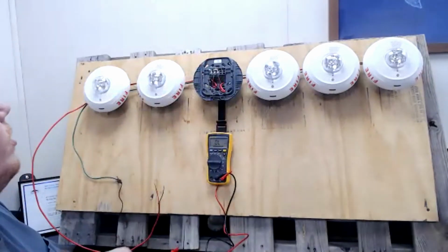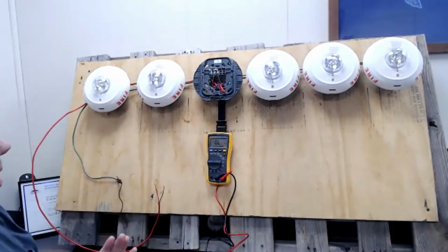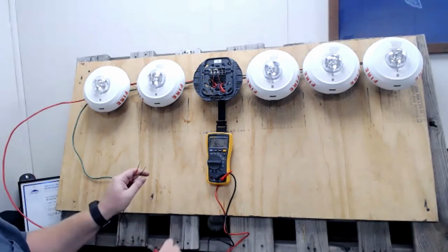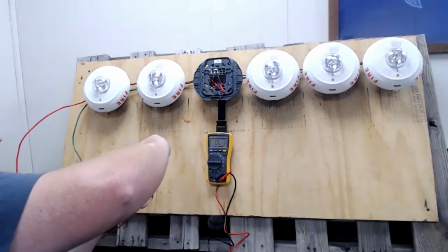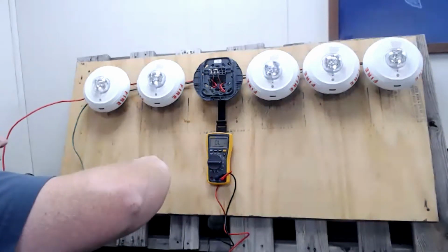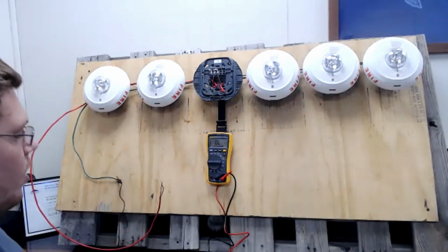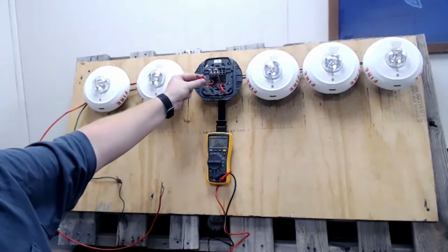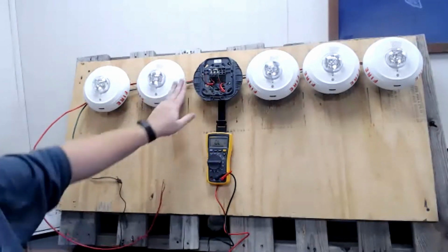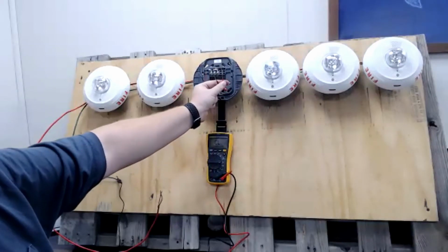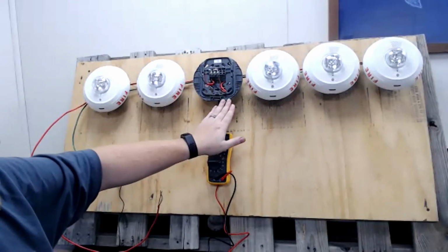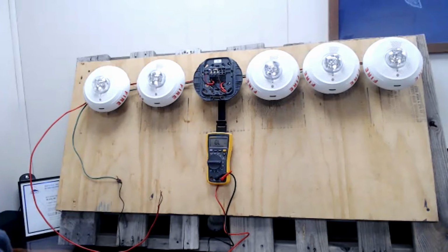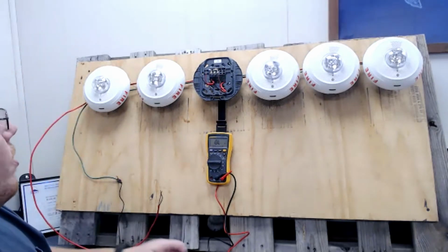All right, now what I want to look for is whether I can see either back to my home run or all the way over to my end of line resistor. So to do that, I need something going on at my home run so I can identify it. So what I'm going to do right now is twist these together to create a short. Looking at these wires, one direction, which will be this wire because we can see it comes back this way, I should be able to see a short. If I can see a short, then that tells me everything from here to here is good. From here, I want to be able to see my end of line resistor. If I see my resistor, that tells me from here to here is good. So one of these sides of the circuit is going to have a problem. And that's what we're looking for right now, which half of the circuit our problem is in.